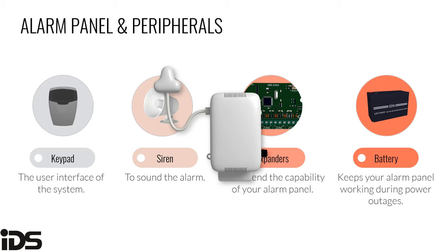All alarm systems must have a transformer to supply power to the panel. For IDS, we use a 16-volt AC transformer. Always check the manual for the correct transformer specifications. Transformers are rated in volt-amps (VA) — this is the amount of current draw they can supply at any given time. A 16-volt AC transformer rated at 40 VA can supply 2.5 amps. Never draw more current than your transformer can supply — this can damage the transformer and potentially cause a fire hazard.